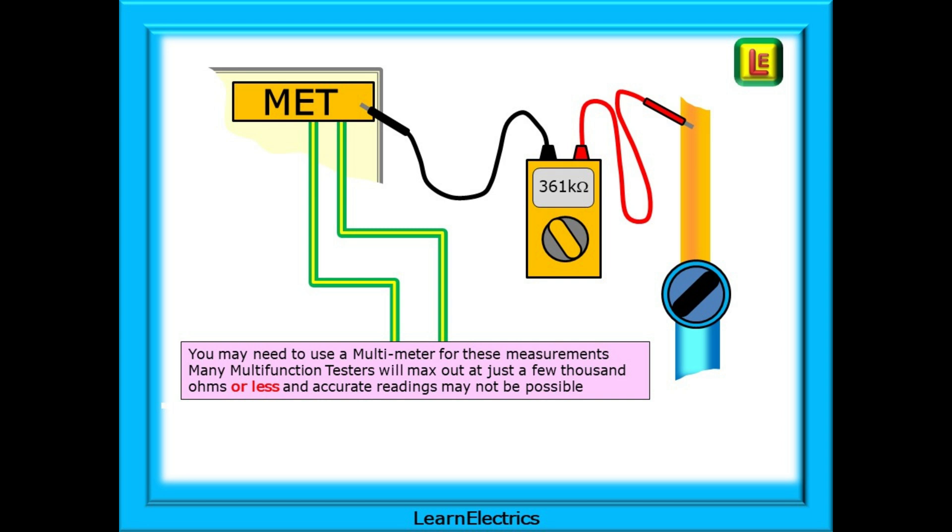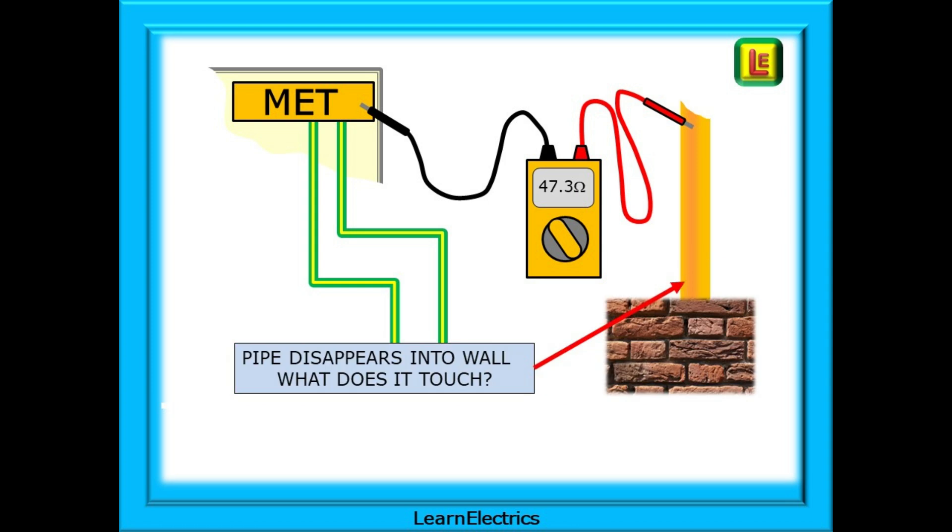Shown here is a copper water pipe inside the house that is supplied by a plastic service pipe. Ideally, we should visually inspect the whole length of the pipe, but what happens when it disappears from view inside a wall? We must measure the resistance value.